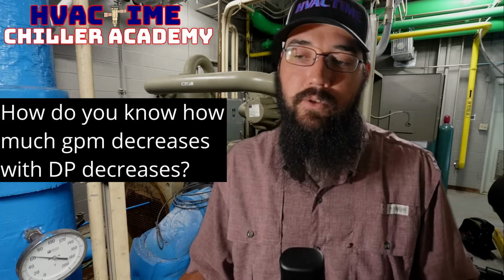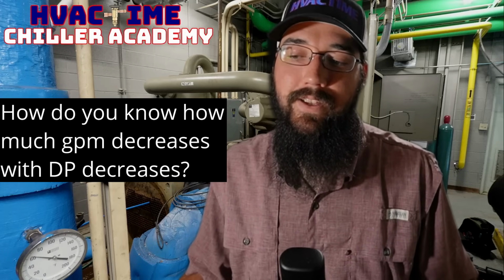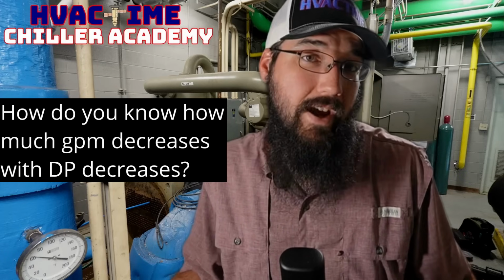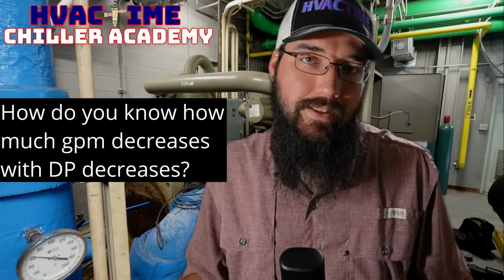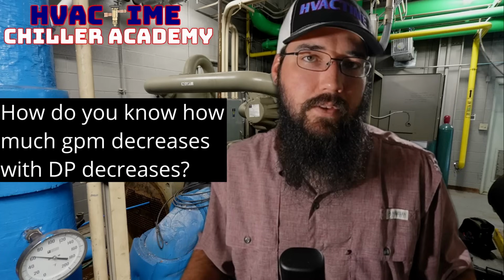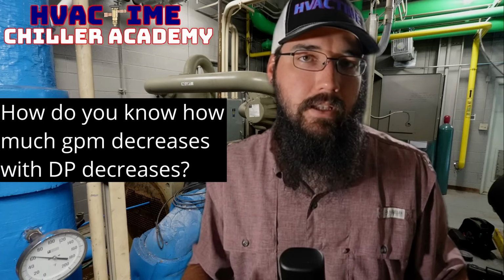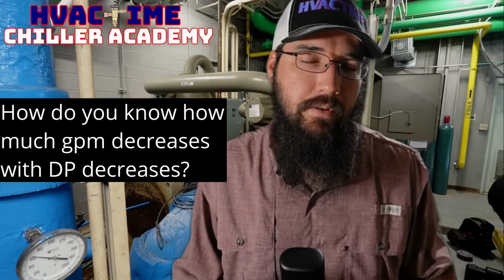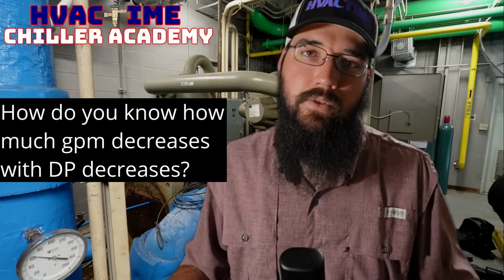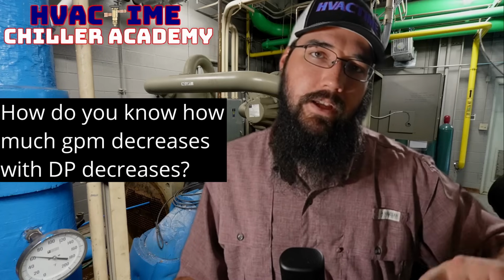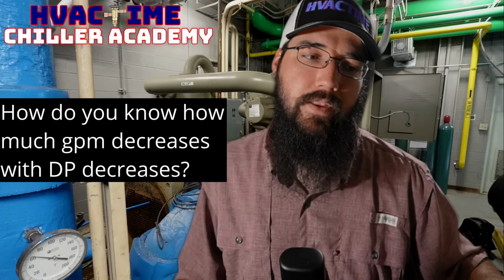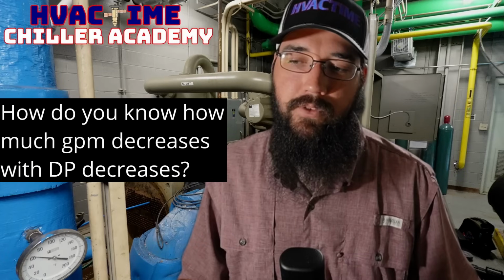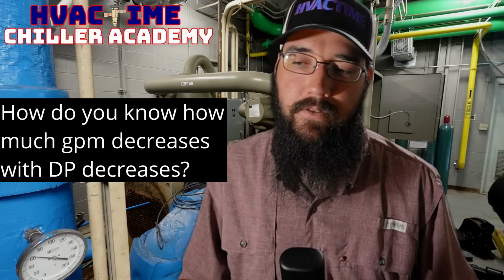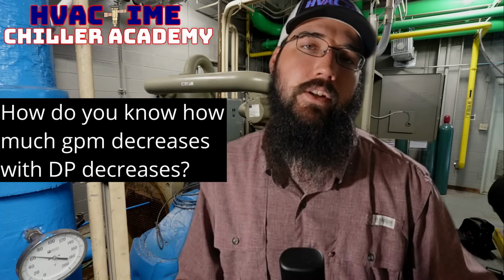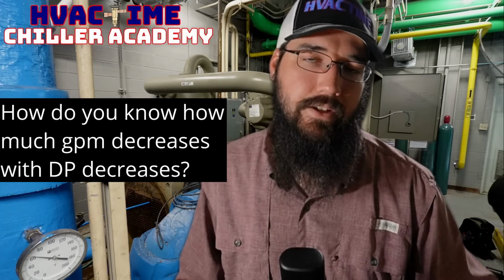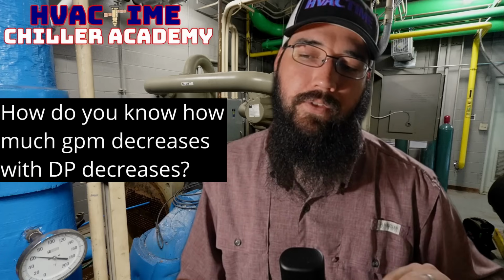That may be true to some degree. I would venture to say that that may be true for a particular manufacturer. My gut tells me it would not be true across the board. Different manufacturers—it depends on how many plates, the gaps of the plates themselves. There's a lot of variables that go into determining what that flow curve looks like, and the pressure drop needed for that flow curve. So I don't think that's a rule of thumb everybody follows. That's an engineering level decision they make when designing that heat exchanger.